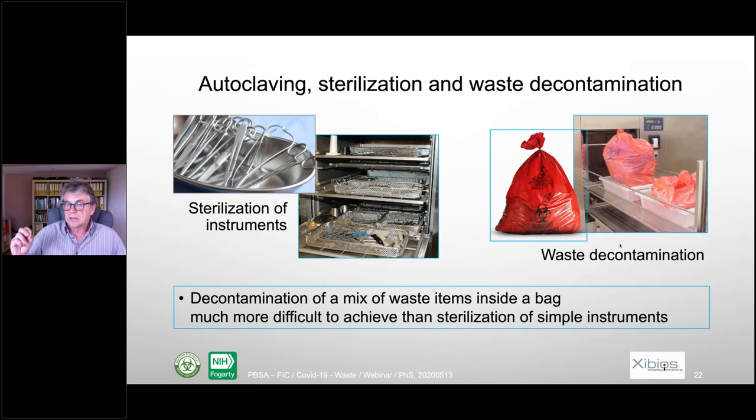So actually, decontamination of complex loads like waste bags is much, much more difficult to achieve than sterilization, because the steam has some difficulties to penetrate the bags and to reach everything inside of the bags.